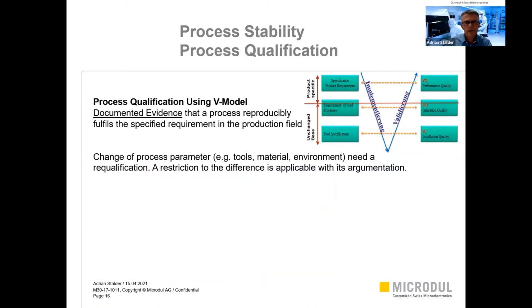To ensure the process stability at Microdul, there are different ways, and we decided many years ago to use the V model for all our process qualifications. Here you see the V model. It starts with the installation qualification on the equipment, and operational qualification and performance qualification. What does qualification mean? Qualification is simply having documented evidence that the process is reproducible and, of course, fulfills your requirements. The requirements which are the specification, and also fulfills finally the requirements of the assembly, of the equipment and of the operator.